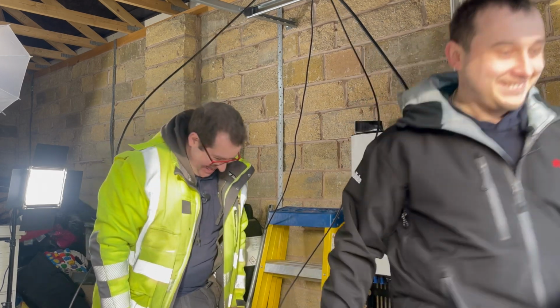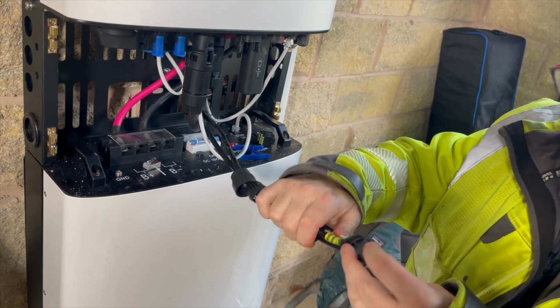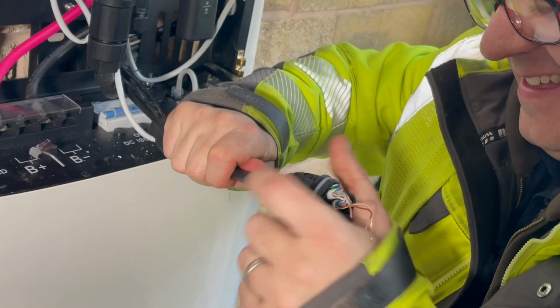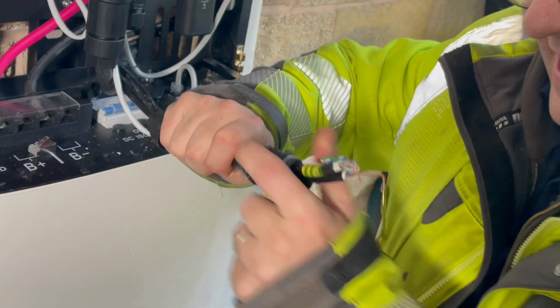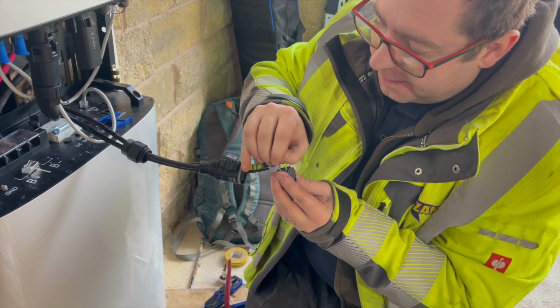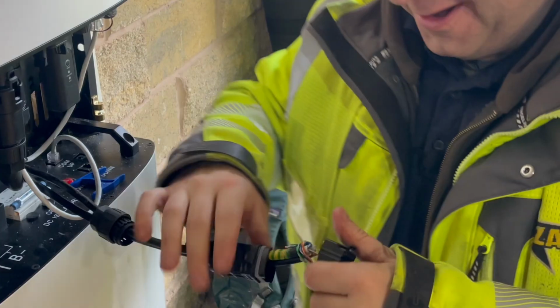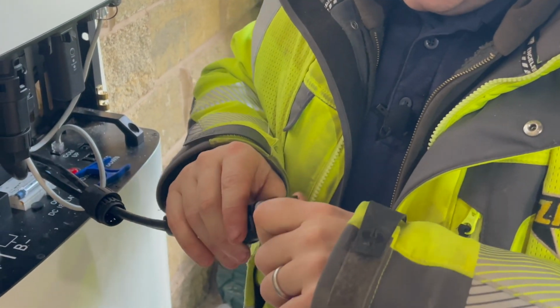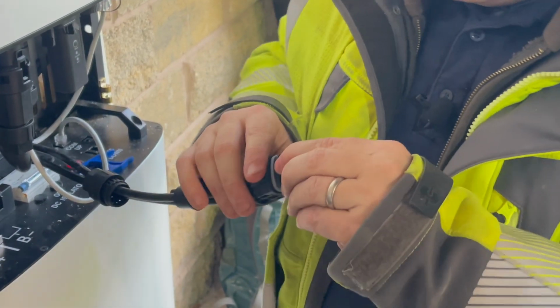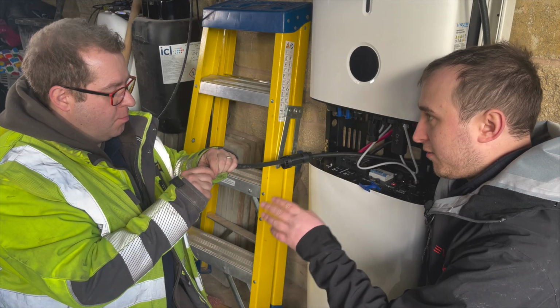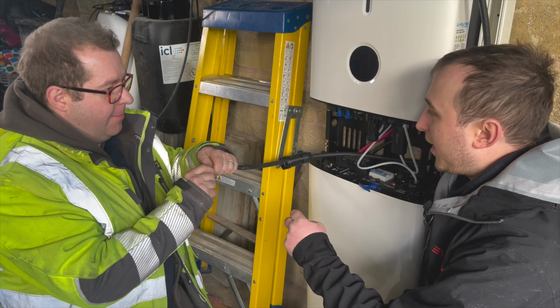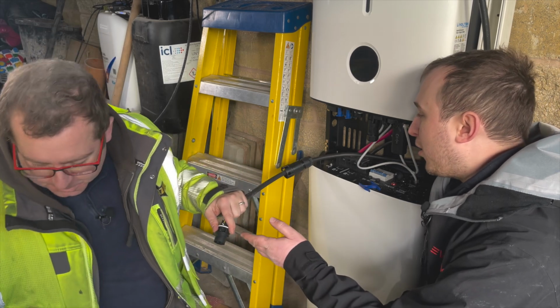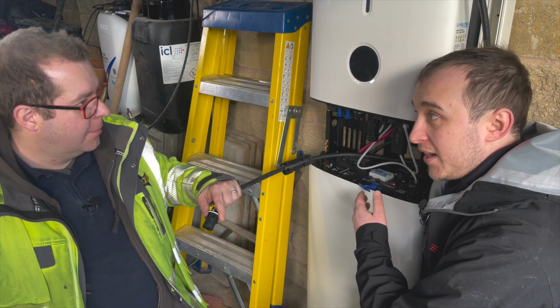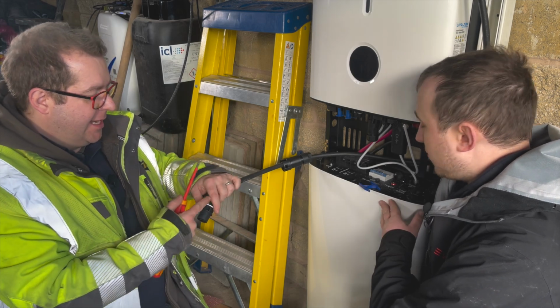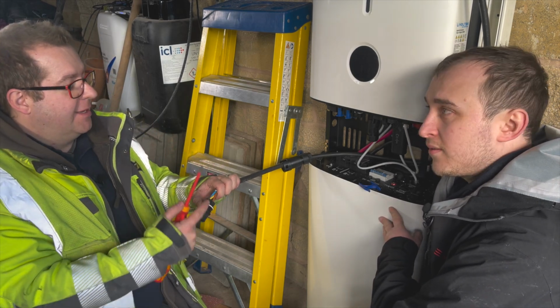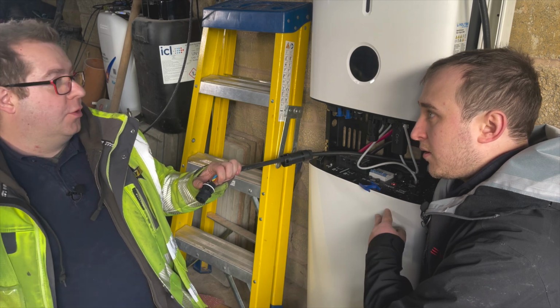So this connection here, Lee, what is this? The grid connection. So is this grid going in? Yes, this is grid going into the inverter, and there's a separate one coming out for the EPS side. So feeding the grid is just one connection in. If you had a power cut, it will only power the EPS side, because it disconnects the grid side to prevent anybody working on the lines getting a shock.